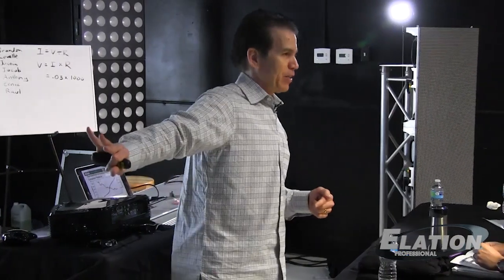If there's a possibility it could rain, dew on the ground, or a sprinkler system coming on, and you're outdoors, personally I think we should be using GFCIs for all our backline gear. That means amplifiers, keyboards, PA system. Well, maybe not big giant PA, because it's expensive and sometimes hard to get PA to work with GFCIs, since audio systems generate harmonics that have trouble working with GFCIs. But you should at least try to get it on GFCI, because that would totally eliminate electrocutions like those we've discussed previously.